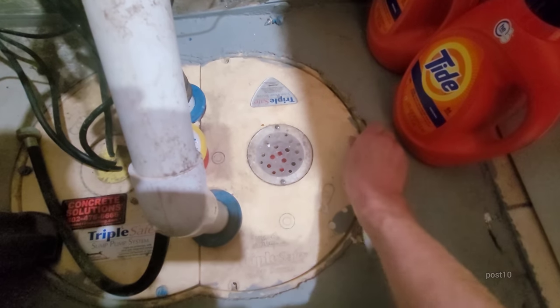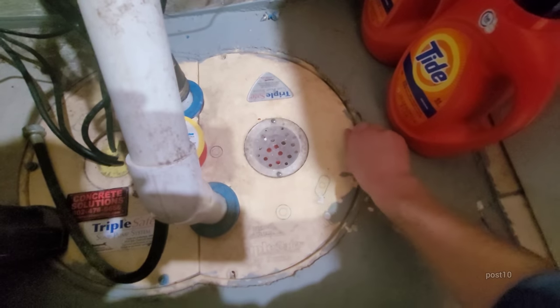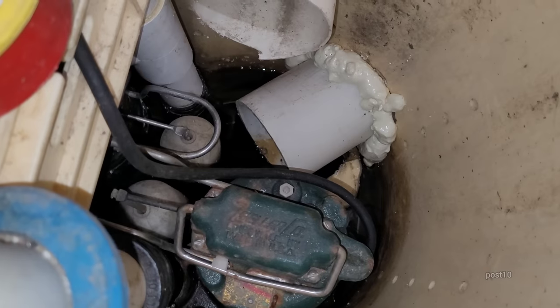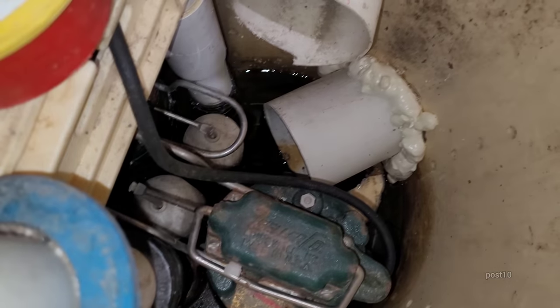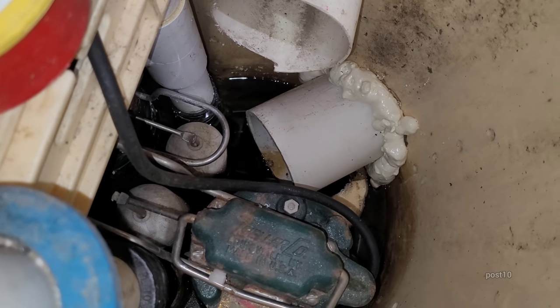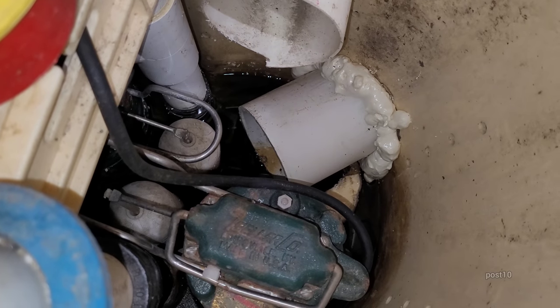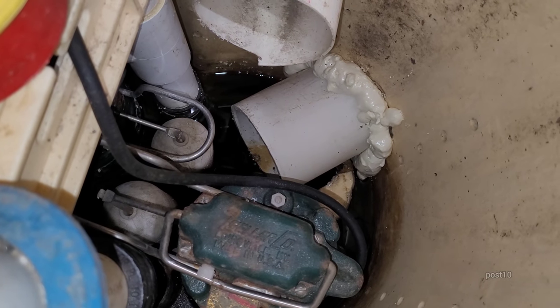It's the last couple days in November and I'm already starting to have an issue that I thought may have been a problem. I was hoping it wouldn't be, but it is. Here inside the sump pump pit this year, I installed this gravity drain line. And if you look in there, you can see there is a tiny bit of water that is trickling into the system. It's already left a little brown water stain going through the entire 150-foot pipeline, and the end of it is starting to form an ice dam. I'm going to show you my solution to this.